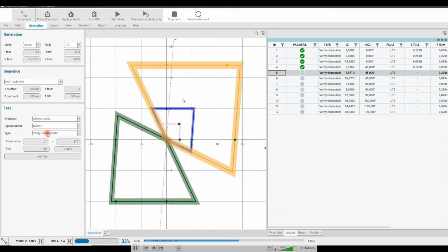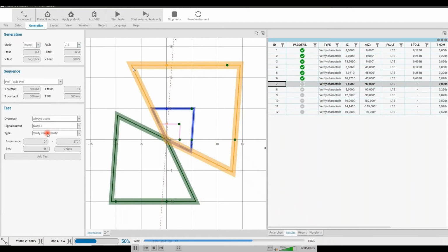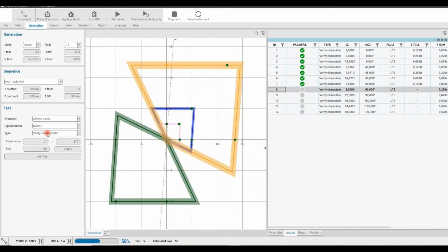border. So in case we are doing a test, for example, here, the direction will be perpendicular. This is important in order to get the most reliable trip time, because it's not convenient to test this border using the same angle of the border. The trip time will not be reliable at all.